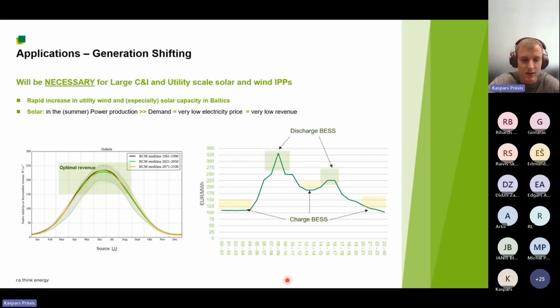consumption periods. So this means that if you add a battery energy storage solution, you can do generation shifting, which basically means that during your highest generation peak, you store this energy in the battery, and when the electricity price is higher, you release it to the grid. So I have tried to depict this in this slide. And by this, you can avoid, let's not call them losses, but low revenues that you would have if you wouldn't have such battery systems. And this would probably also reduce the return on investment for the whole solar or wind plus battery system itself. So there are great financial benefits in using this kind of system for these projects.